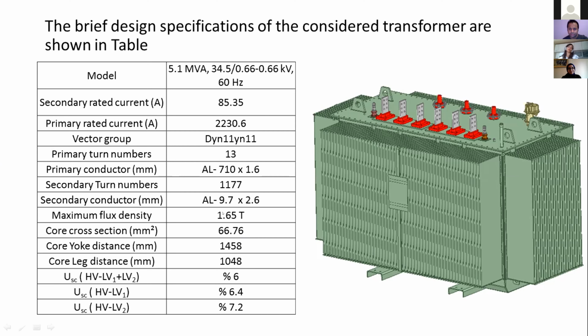The maximum flux density of the core in our transformer is about 1.65 Tesla. The short circuit impedance at full power, I mean 5.1 MVA, is 6%. The short circuit impedance of the high voltage winding and inner low voltage winding is about 6.4%, and the short circuit impedance of the high voltage and outer LV winding is about 7.2% in our model and our transformer.